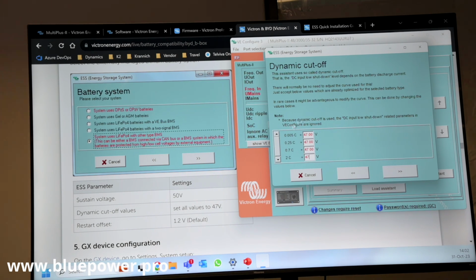What this does is, at the given discharge rate, the inverter ignores the disconnect parameters and can disconnect at that voltage. So for this battery, no matter the discharge rate, it's going to reach close to 0%, maybe 5% SOC, at 47 volts guaranteed.